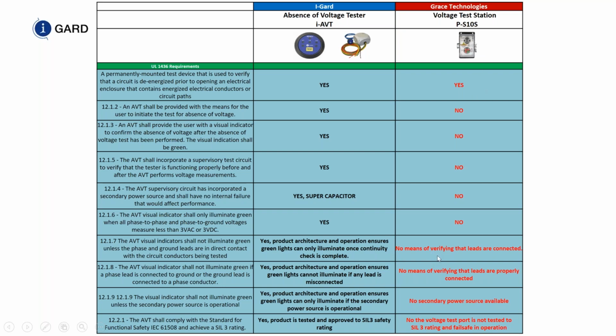With the voltage test station, there are no means to detect whether the system is connected properly or not. The absence of voltage indicator shall not illuminate green if the phase leads are connected to ground. Yes, we can ensure that there's no misconnection, but if there was a misconnection, it's not really installed to manufacturer specific instructions, and you can test for that initially. With this test station, no, you can't.